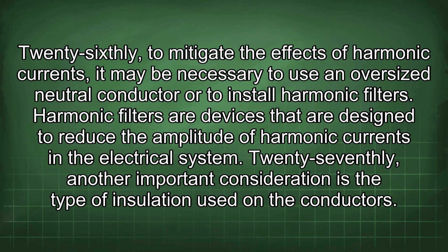26thly, to mitigate the effects of harmonic currents, it may be necessary to use an oversized neutral conductor or to install harmonic filters. Harmonic filters are devices that are designed to reduce the amplitude of harmonic currents in the electrical system.